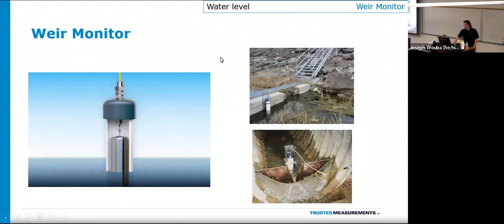So then we'll get into a weir monitor briefly. This is also a vibrating wire instrument. The vibrating wire transducer itself hangs at the top of the stilling well. These are very accurate instruments. They're used to measure water level very accurately, typically less than a millimeter, in weirs, shallow streams, shallow reservoirs even, typically 6 feet and under. So how these work is they have a weight that hangs on this vibrating wire transducer at the top of the stilling well. Stilling wells are installed inside the weir or inside the reservoir or stream. And as that water level changes, the buoyancy on that weight changes, which in turn changes the tension on that vibrating wire. You get a very accurate water level measurement.